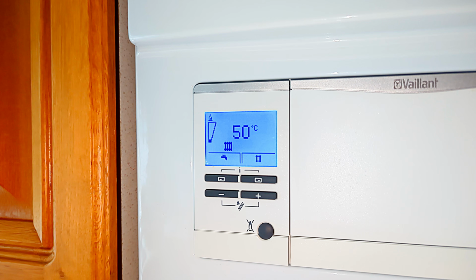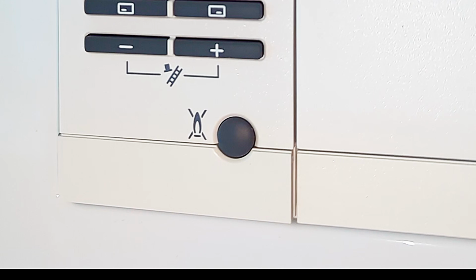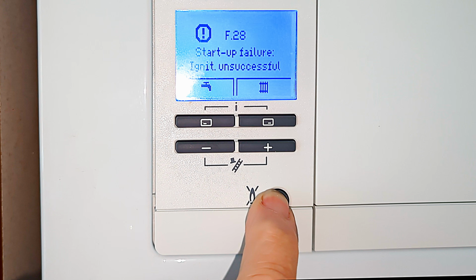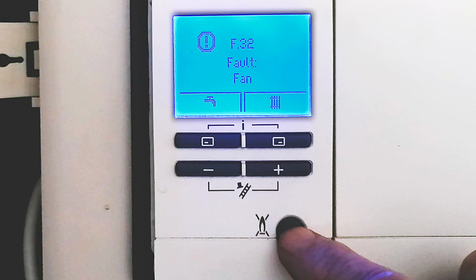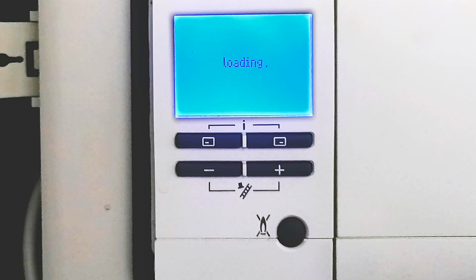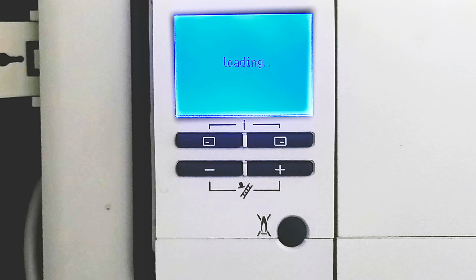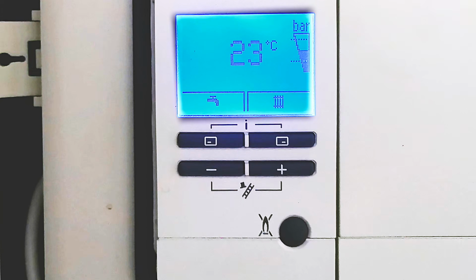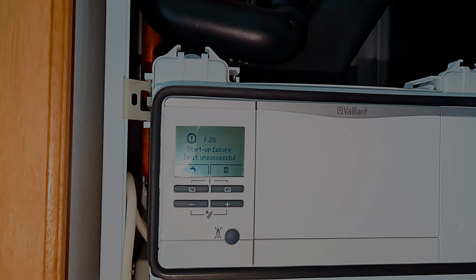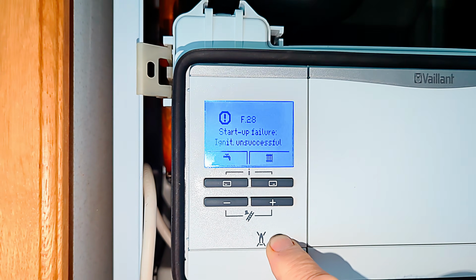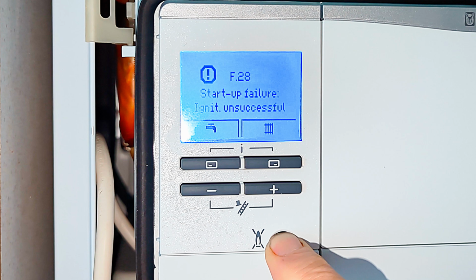It's worth noting that if you get any fault code on the display, the only way to reset the boiler is to press the reset button and hold it for 5 seconds until the boiler says faults cleared. Now here's an F32 fault, which is a fan fault. On some of the Vaillant combination boilers, all you need to do is just press the button. You don't actually have to hold it for 5 seconds. Now this boiler has come up with the fault code F28, or it could also be an F29, but F28 stands for it's tried to light 3 times and for some reason it's failed to ignite.